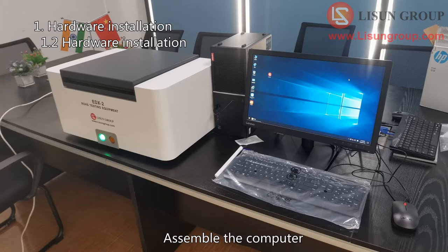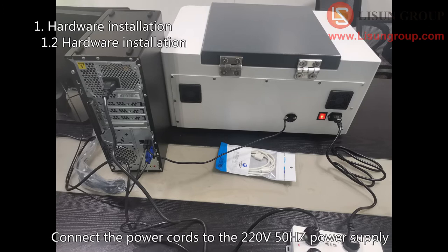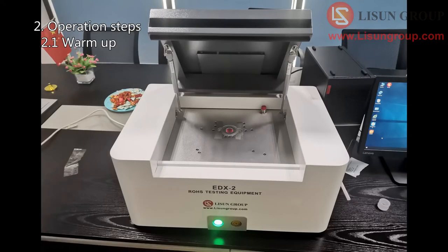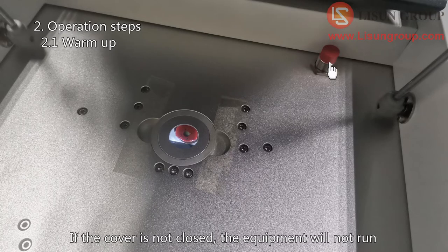Assemble the computer. Connect the USB cable on the back of the equipment to the computer. If the length is not enough, you can use the USB extension cable. Connect the power cords to the 220V 50Hz power supply and turn on the equipment and computer. Open the cover of the RoHS testing equipment. Here is a safety sensor switch — if the cover is not closed, the equipment will not run.